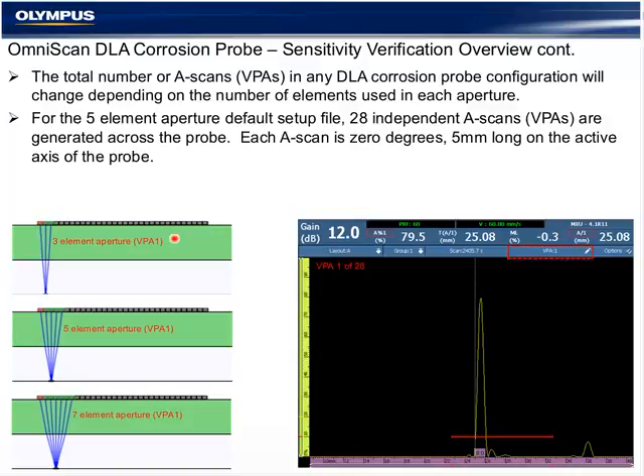As a 1 millimeter pitch probe, that's going to give us a virtual probe aperture of 3, 5, and 7 millimeters. Because these are fixed configuration files, this probe is not compatible with the setup wizard built into the OmniScan. It's dependent on modification of one of the default files for use.